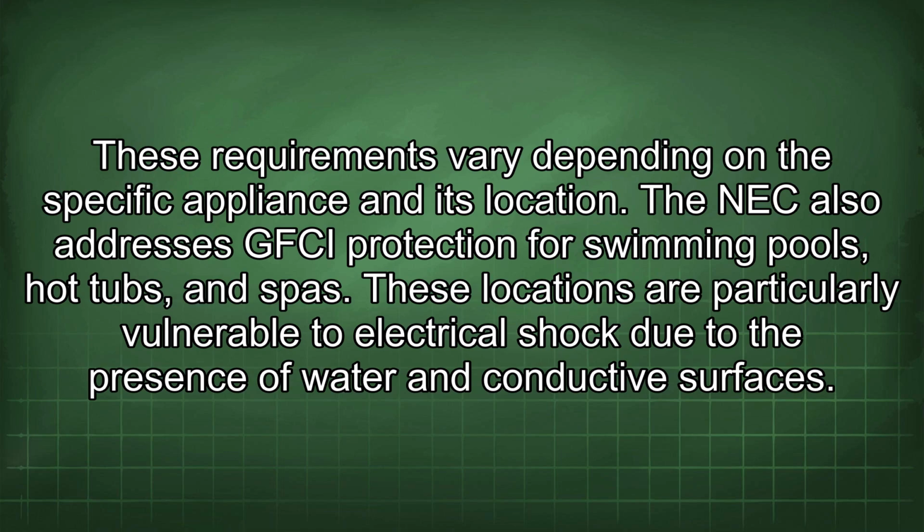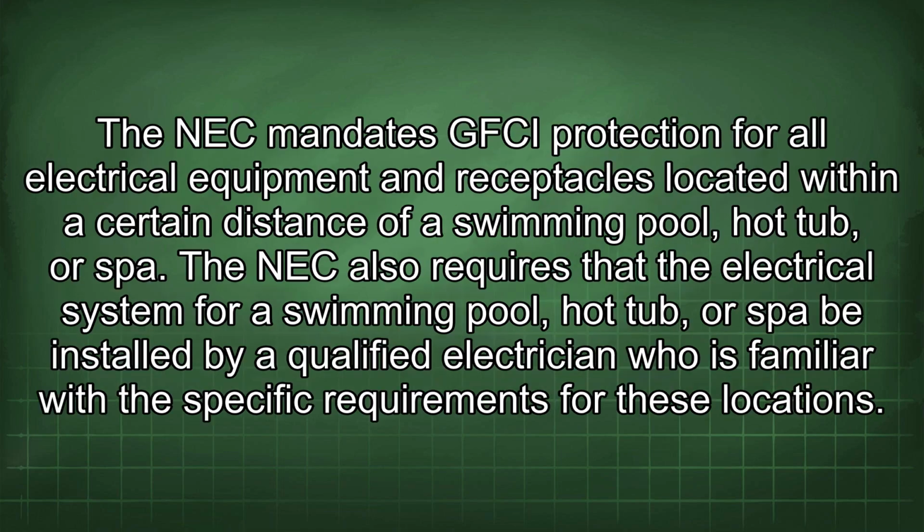These locations are particularly vulnerable to electrical shock due to the presence of water and conductive surfaces. The NEC mandates GFCI protection for all electrical equipment and receptacles located within a certain distance of a swimming pool, hot tub, or spa. The NEC also requires that the electrical system for a swimming pool, hot tub, or spa be installed by a qualified electrician who is familiar with the specific requirements for these locations.